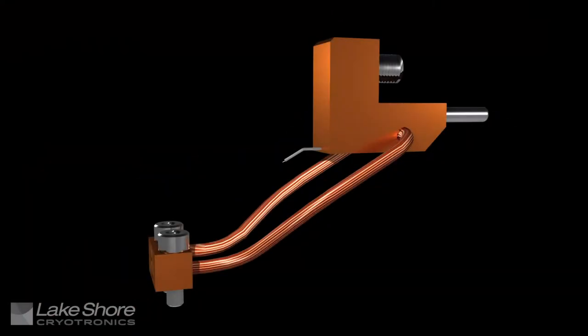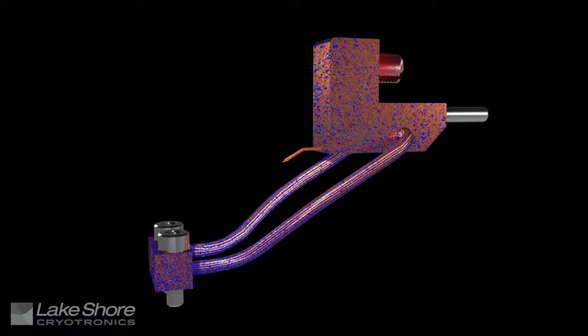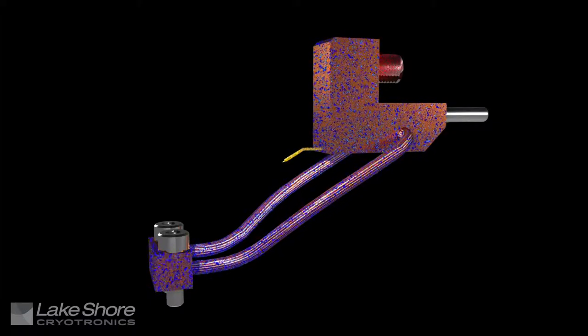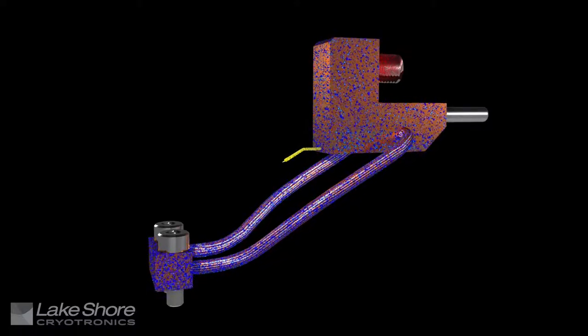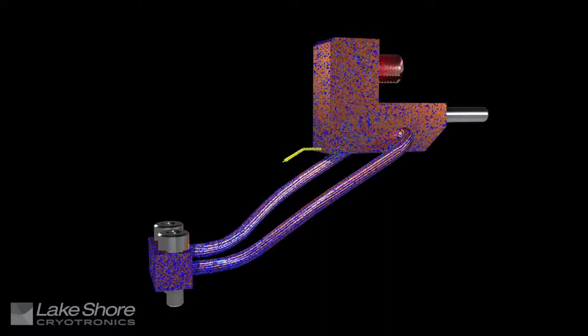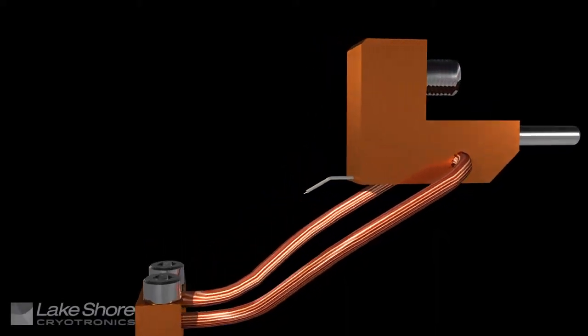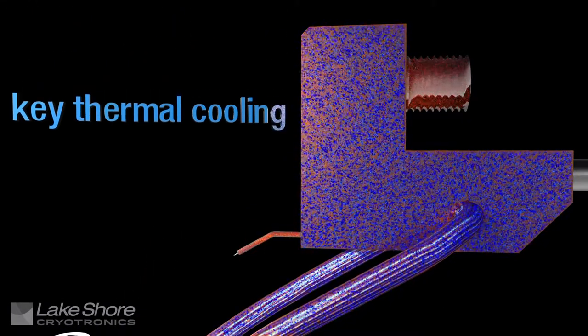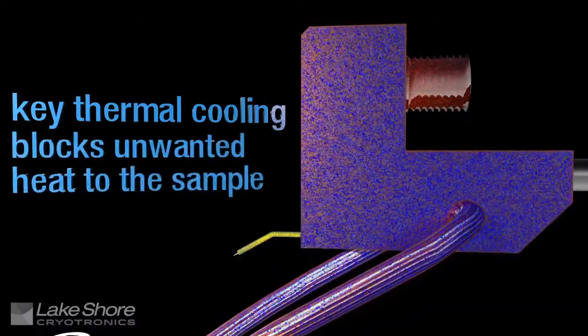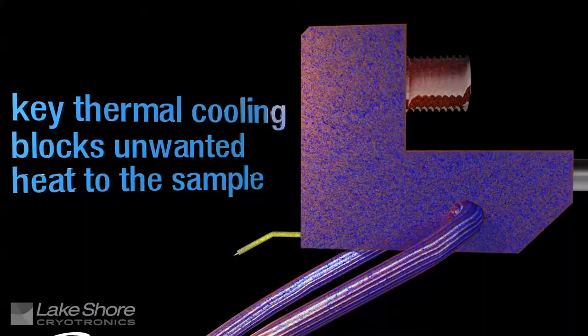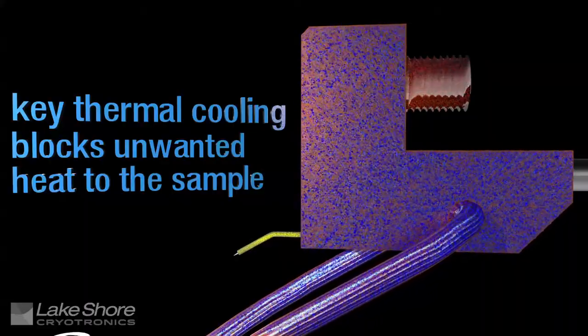This process will be performed on a Lakeshore GSG microwave probe. Lakeshore microwave probes differ from other RF probes in that they have an integrated mount, all-copper body, and a pair of copper braids that are attached to the sample stage via a copper braid block to cool the probe. This design provides key thermal cooling of the probe tip and blocks unwanted heat to the sample, and Lakeshore microwave probes are routinely cooled below 10 Kelvin in a CRX 4K probe station.